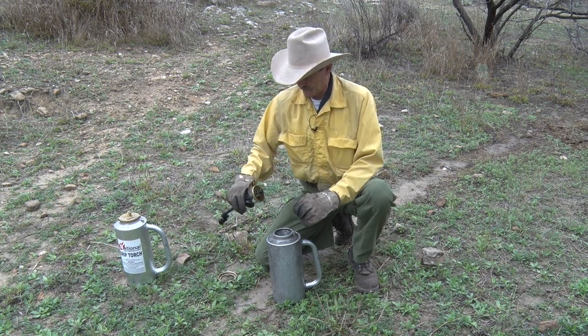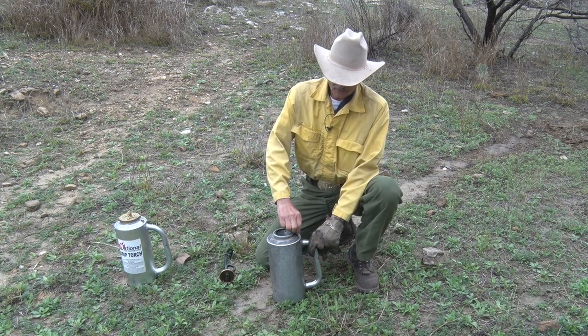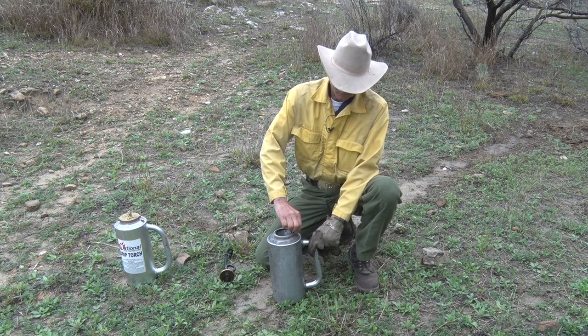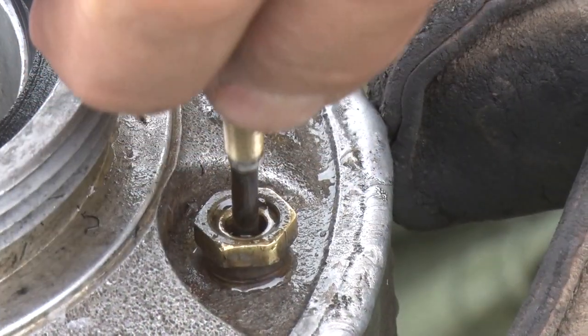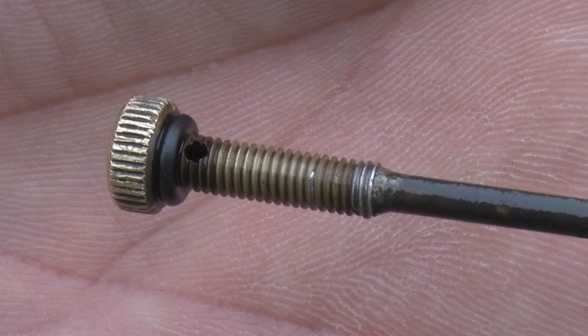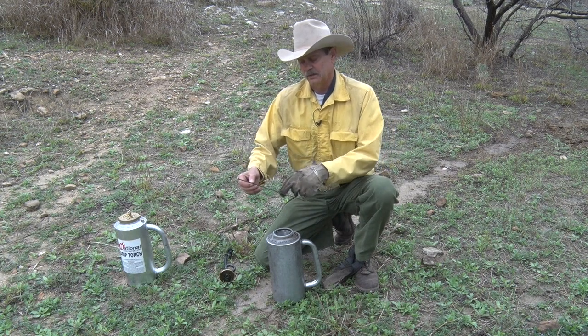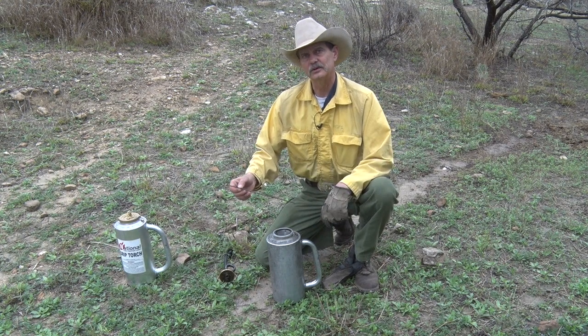One of the final things to look for when troubleshooting is the air vent valve here that allows the fuel flow mixture. You can unscrew this thumb screw out of this nut and you should be able to get air coming through this stem through two small holes here in the top. You can run a small wire down through there or even blow through there to unclog that air vent tube if you're not getting a fuel mixture running out through your ignition device.